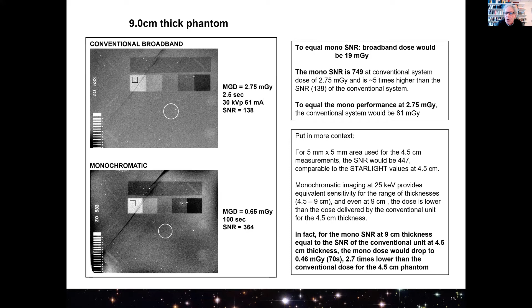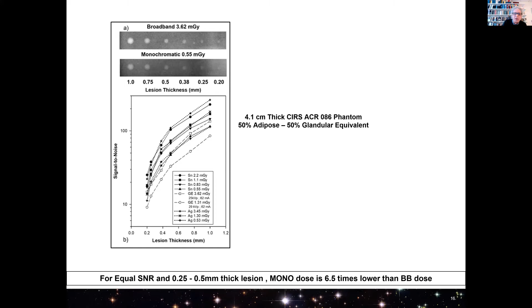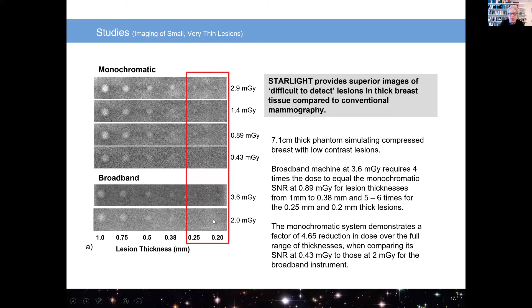Here are some examples of looking at more difficult, very thin lesions, ranging in thickness from 1 millimeter to 200 microns. And these are the signal to noise values. For the 1/4 millimeter and 0.5 millimeter thick lesions, the monochromatic dose is 6.5 times lower than the conventional dose. And to really challenge the two systems, we looked at these same very thin lesions in a 7 centimeter thick compressed breast, and we're 4 to 5 times lower in dose, even all the way down to, you can see, very difficult for the broadband machine to see the 200 micron thick lesion.